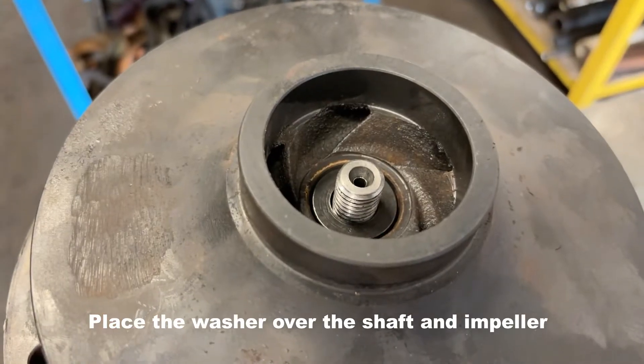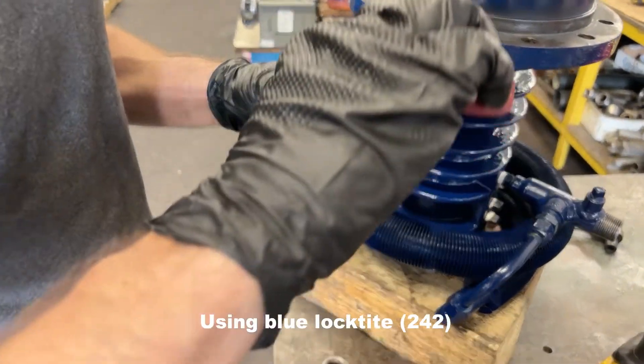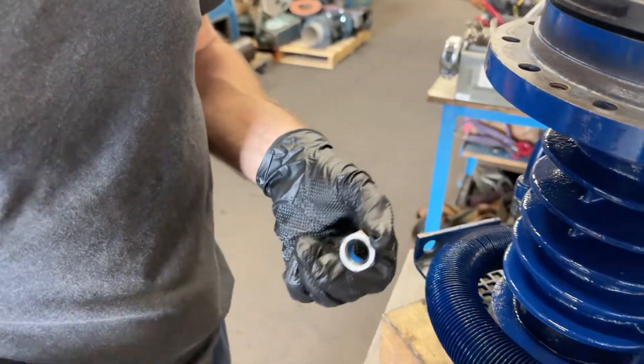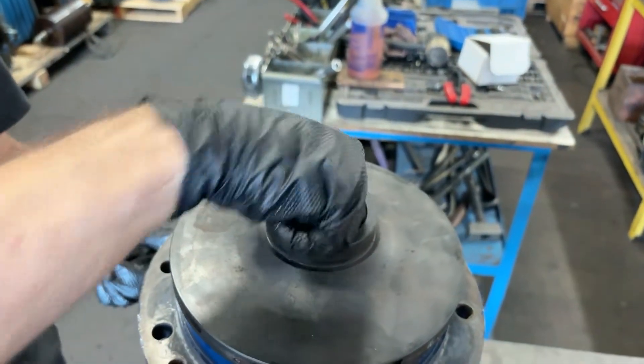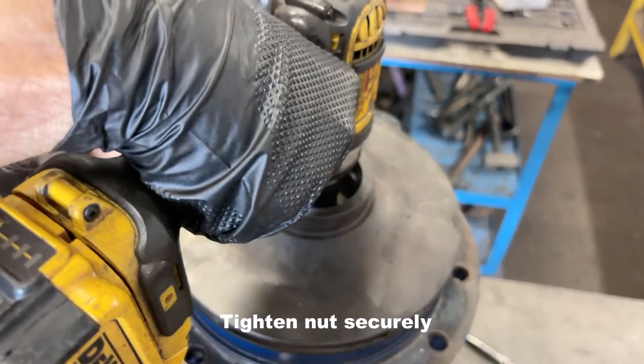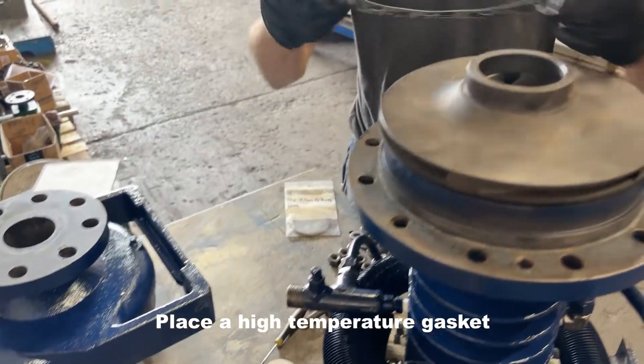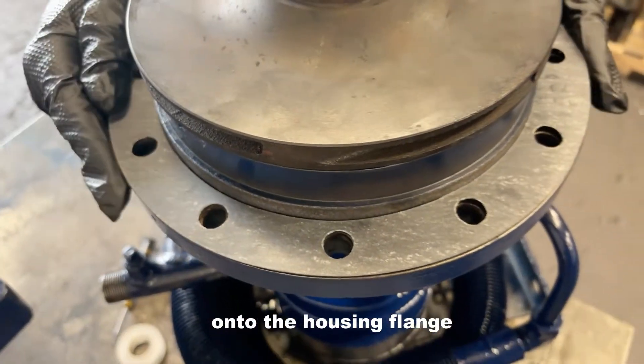Place the washer onto the top of the shaft. Using blue Loctite, thread the nut onto the shaft. Place a high temperature gasket onto the housing flange, then install the volute. Make sure you tighten the nuts evenly.